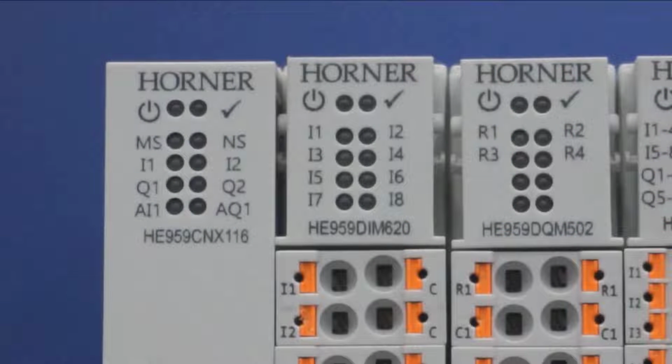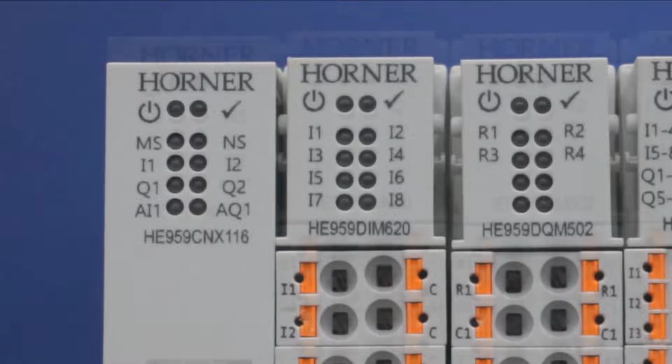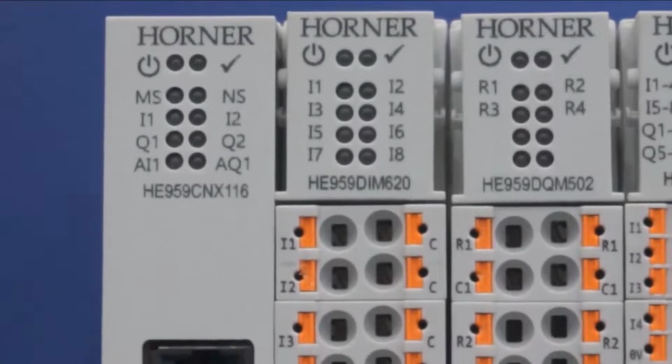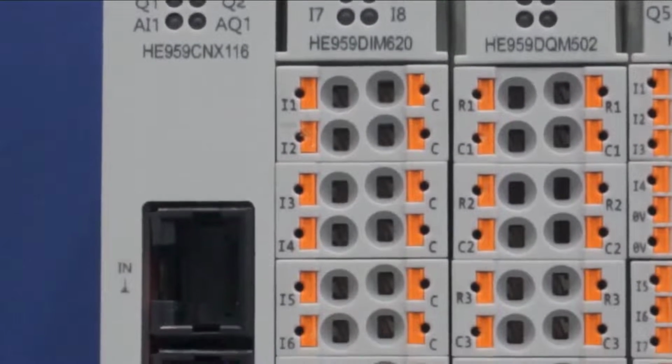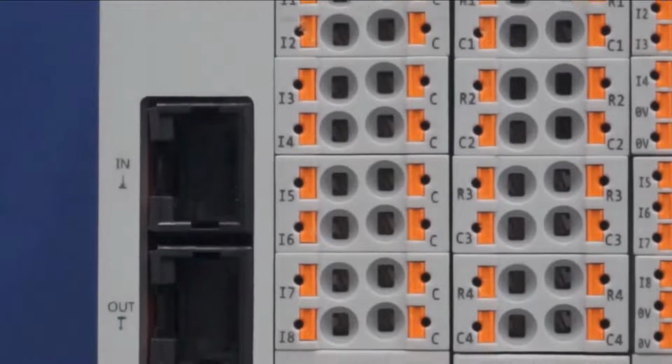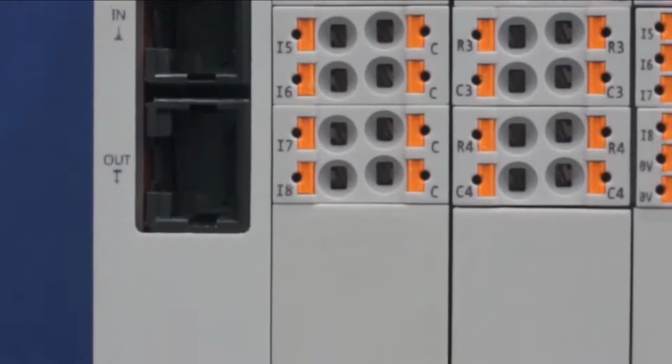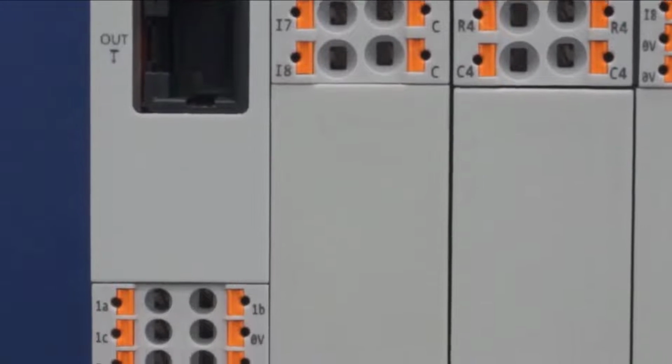At the top of its housing, the CNX base has plenty of LEDs to annunciate its connection status. You'll also notice LEDs dedicated to I/O status as well. That's because the CNX offers a few local I/O points of its own. The local I/O includes a new Horner innovation called flexible inputs, but more on that in a minute. As we navigate to the bottom of the housing, that's where the CNX power and I/O connections are made. The CNX accepts a wide range DC power input so it is compatible with both 12 volt and 24 volt DC power.